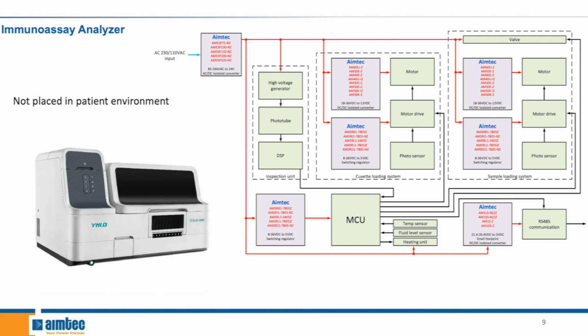Now we can have a look at the Immunoassay Analyzer. This machine is used to identify different substances of interest in a given sample. The basic concept is to use labeled molecules that are coated with an antibody to target substances of interest and highlight them. The labeled molecules will emit light under certain wavelengths, which will then be captured by the photosensor. This captured data is then analyzed to produce the test results.